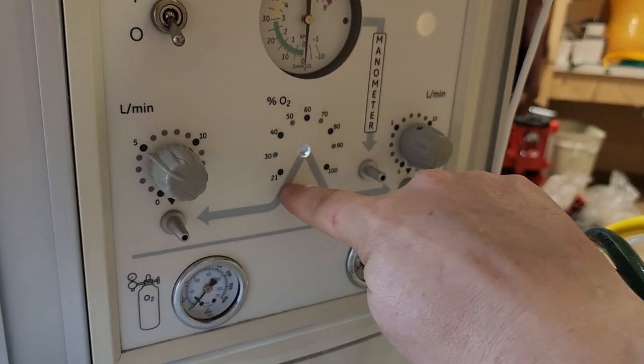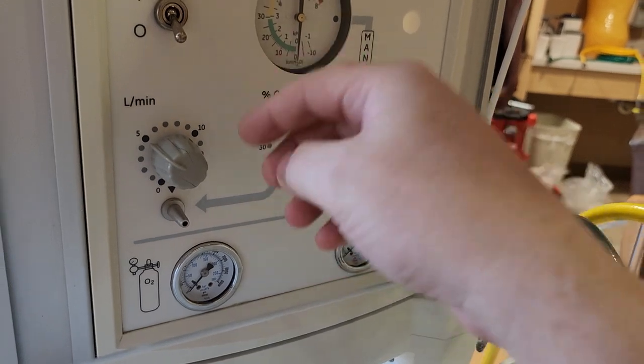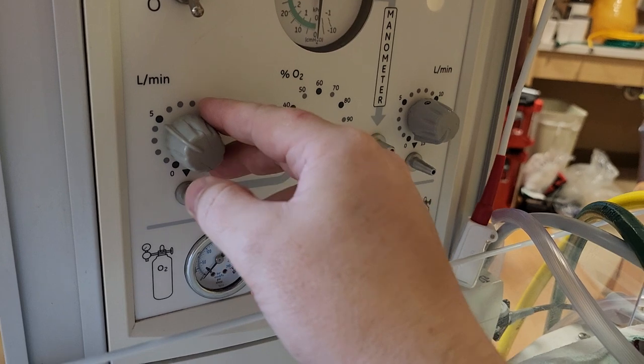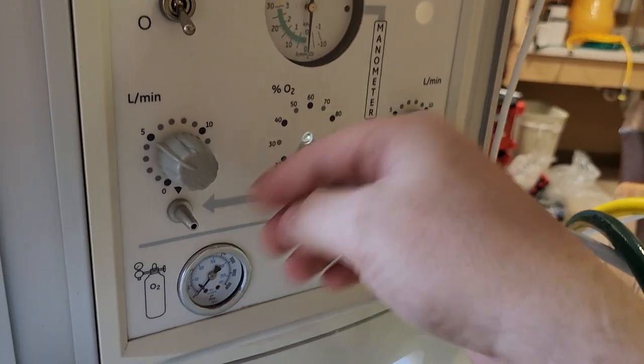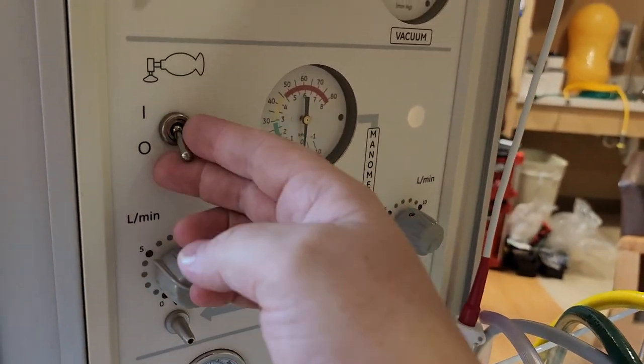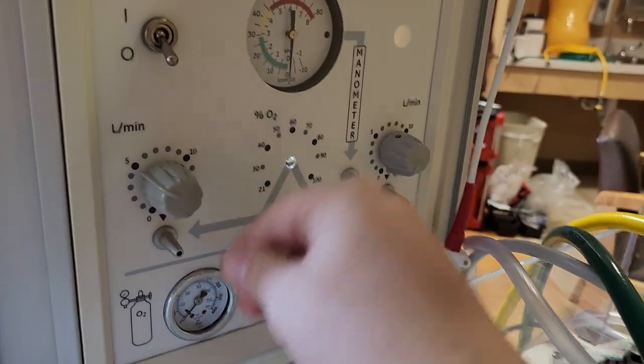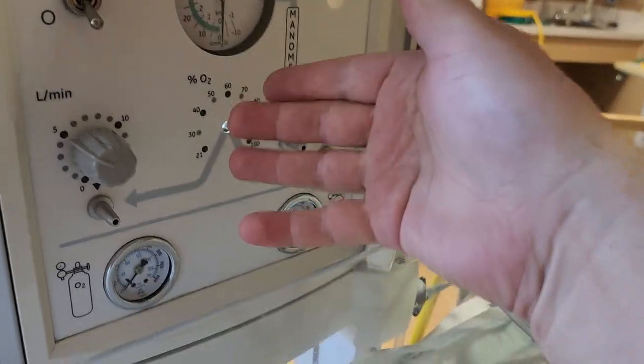So during a regular PM you're shooting 21%, you will definitely see it. It doesn't matter which one of these you try out, but we were testing it at five liters on this port. The key indicator during the PM is when it's in off position we had output, which was really odd. Then we checked the percentages—percentages were off. So let's go ahead and take a look.